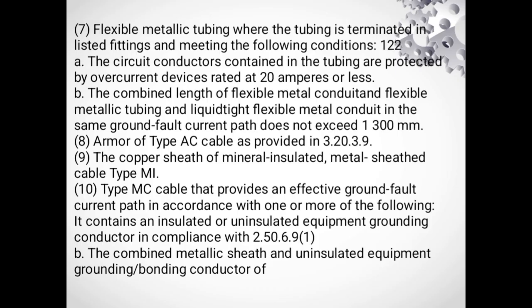7. Flexible metallic tubing where the tubing is terminated in listed fitting and meeting the following conditions. A. The circuit conductors contained in the tubing are protected by overcurrent devices rated at 20 amperes or less. B. The combined length of flexible metal conduit and flexible metallic tubing and liquidtight flexible metal conduit in the same ground fault current path does not exceed 1,300 mm. 8. Armor of type AC cable as provided in 3.20.3.9. 9. The copper sheath of mineral insulated metal sheathed cable type MI.